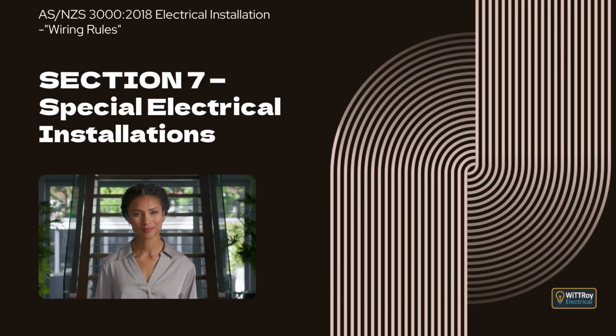It explains that any exposed conductive parts of the electricity generation system must be earthed by connection to the main earthing conductor at the main switchboard. Clause 7.3.7 Connected electrical equipment. This clause explains that any accessory, conductor, insulation or other component connected to the output side of an electricity generation system must be suitable for the voltage, current and frequency produced by the system.